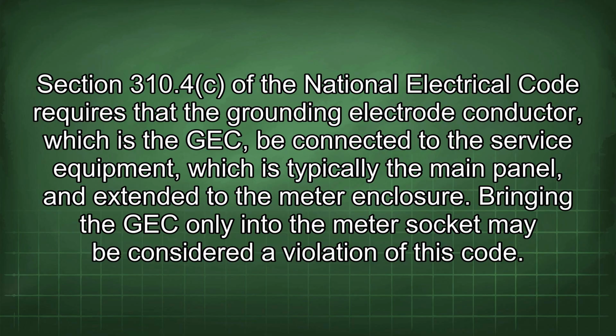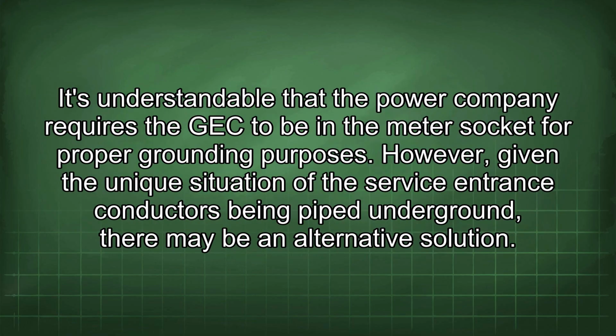Section 310.4 of the National Electrical Code requires that the grounding electrode conductor, which is the GEC, be connected to the service equipment, which is typically the main panel, and extended to the meter enclosure. Bringing the GEC only into the meter socket may be considered a violation of this code. It's understandable that the power company requires the GEC to be in the meter socket for proper grounding purposes. However, given the unique situation of the service entrance conductors being piped underground, there may be an alternative solution.